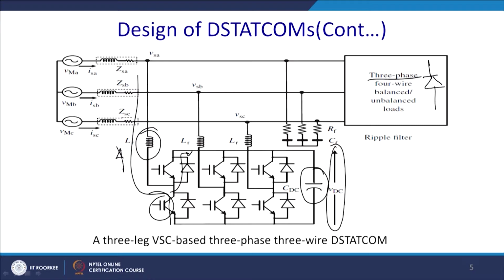So, this LR essentially serves two purposes, since it is a PWM inverter. The instantaneous pole voltage of the inverter will be different from the VSA, and for this reason we have to put in an inductor to block the circulating current, and moreover we require it to boost up the DC bus voltage. So, for this reason we require this inductor.